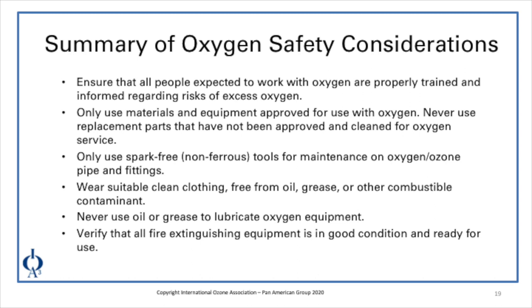Additional summary items: smoking is strictly forbidden in areas where oxygen enrichment is possible. When working in a confined space where oxygen is used, isolate equipment, provide ventilation, and use oxygen analyzers. Entry shall only be allowed by permit issued by a trained, responsible person. Do not enter oxygen-enriched atmospheres to rescue burning victims — victims may be hosed with water from a safe distance and rescued when ambient oxygen is below 23%. If exposed to oxygen-enriched atmospheres, avoid flame or any ignition source until clothing has been properly ventilated.